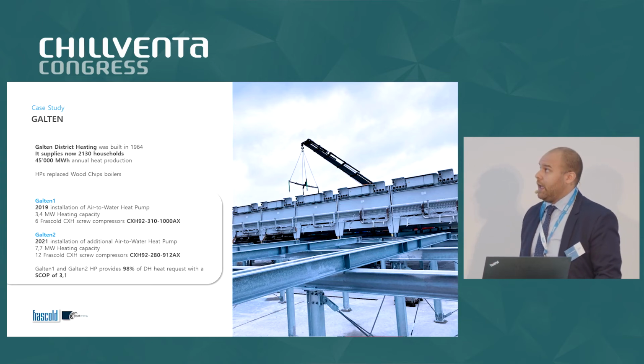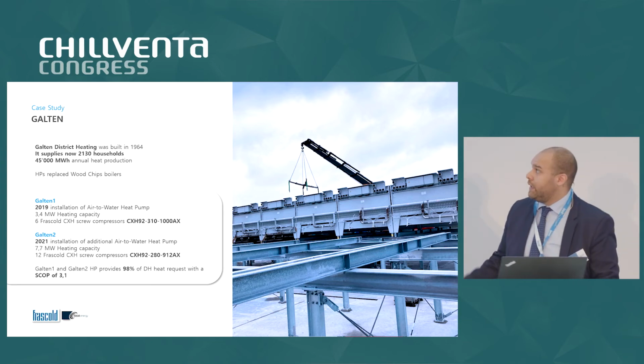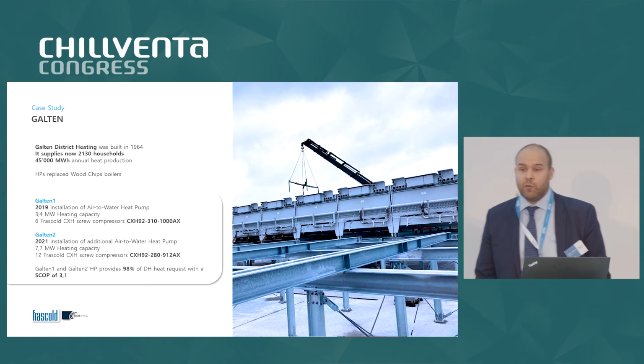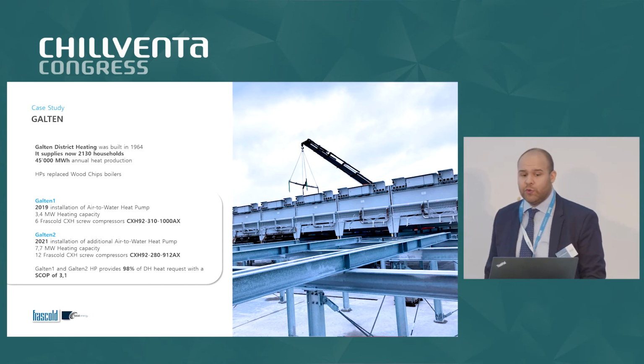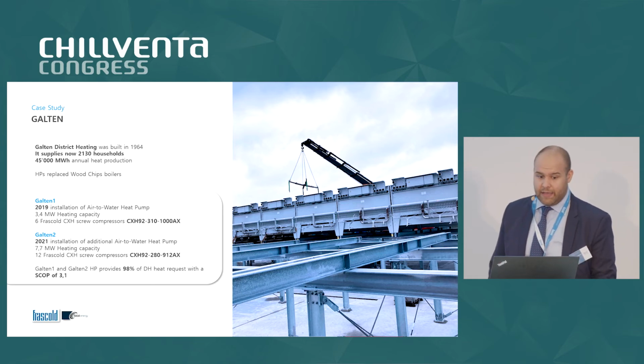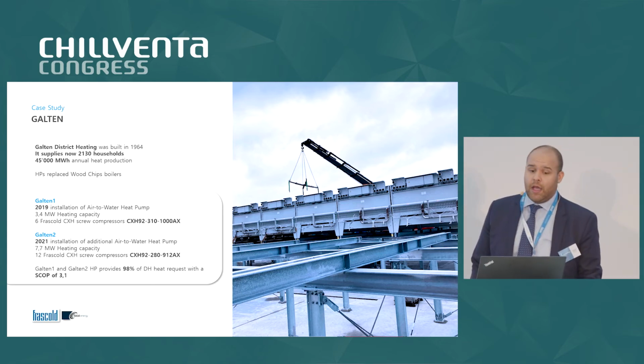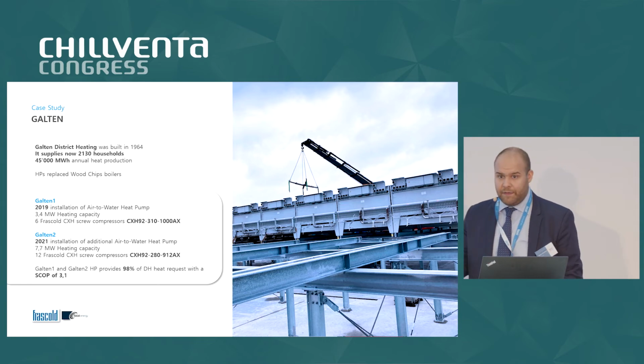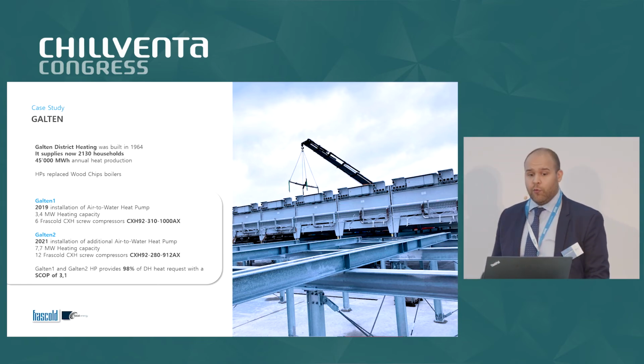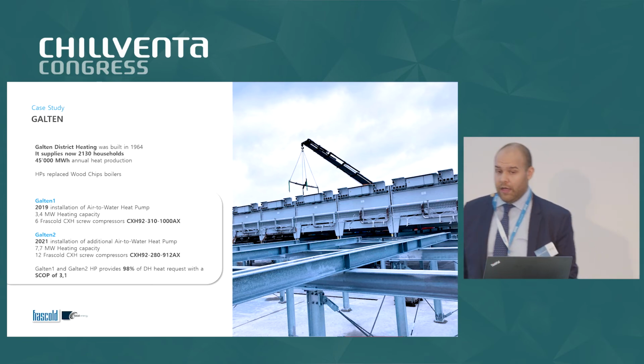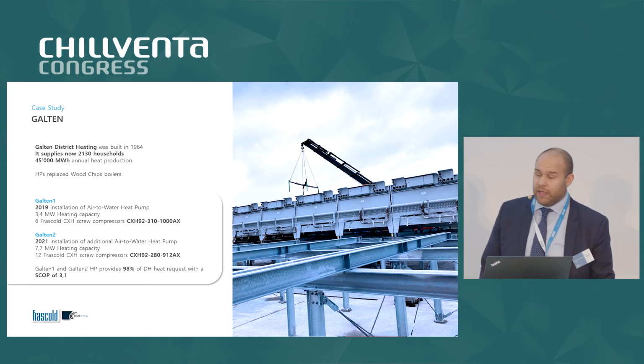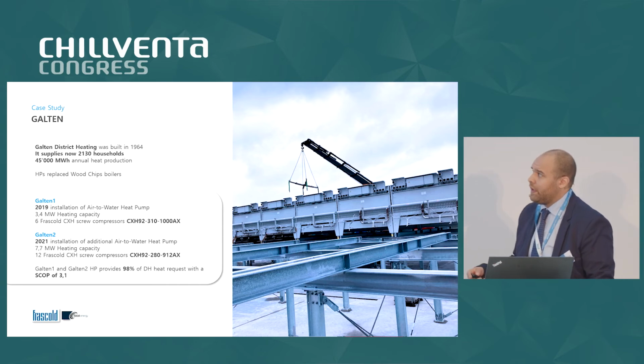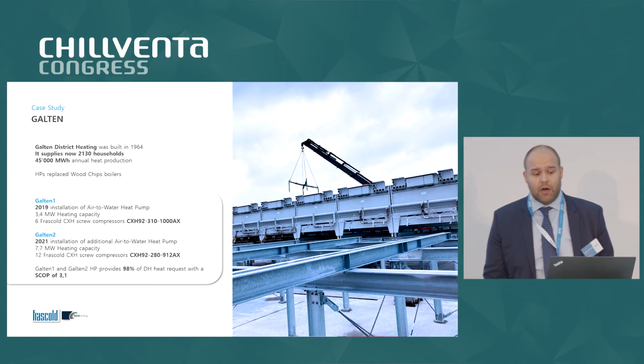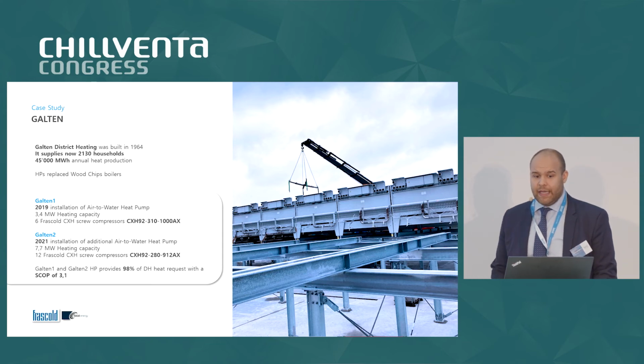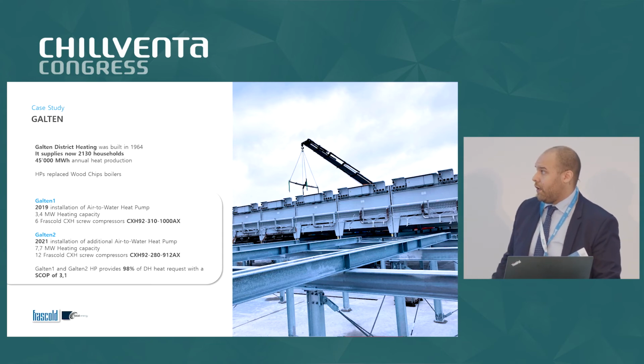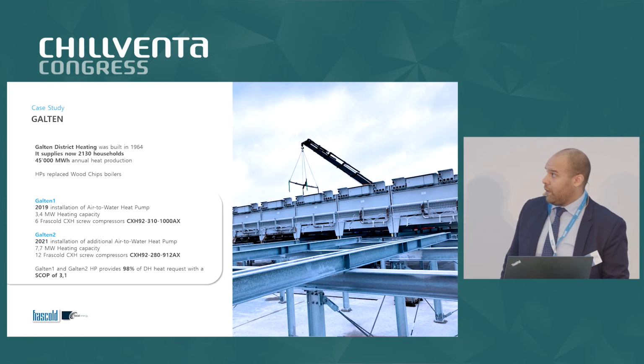The first case study is Galten. Galten district heating, built in 1964, supplies more than 2,000 households and produces 45,000 megawatt hours each year. When the community of Galten decided to replace the wood chip heater with a heat pump, they realized the first heat pump in 2019, an air-to-water heat pump with a heating capacity of 3.4 megawatt with 6 CXH Frascold compressors of 1,000 cubic meters per hour.